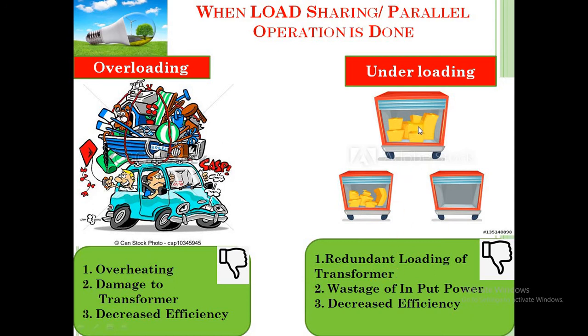Means if we load less than its capacity, then transformer efficiency decreases. Also, as the load decreases, the transformer doesn't take less power from the supply, it will take as much power as it requires, and therefore there is a wastage of input power in the transformer, and because of this there is a decreased efficiency. So in both cases, overloading and underloading, we get decreased efficiency and wastage of power.